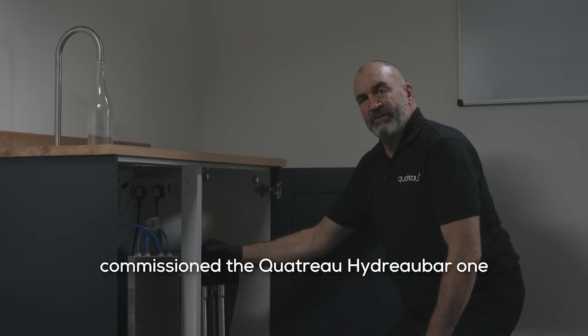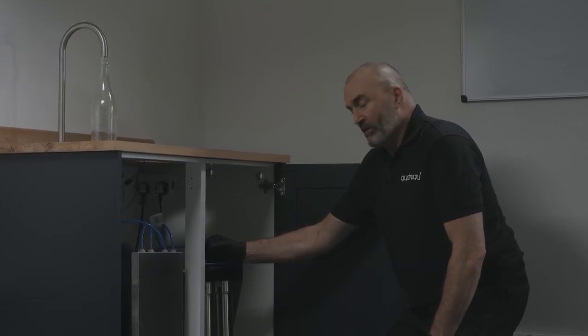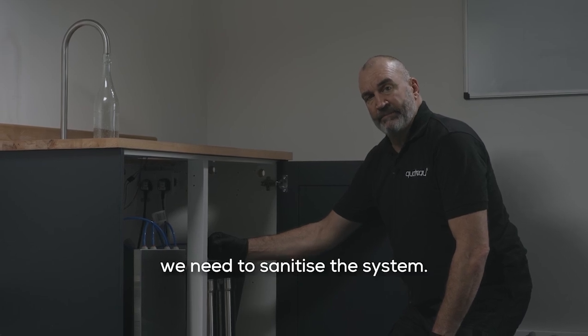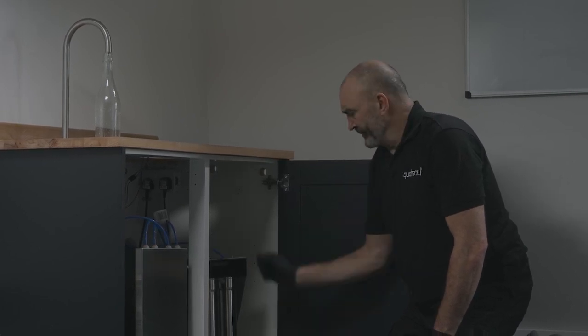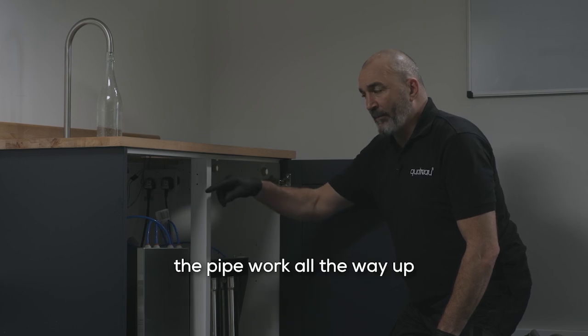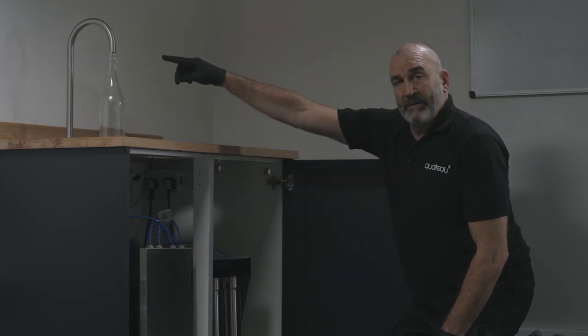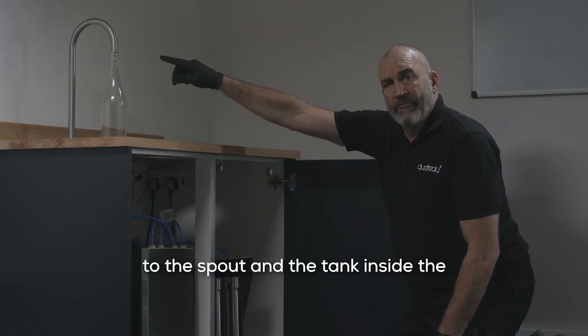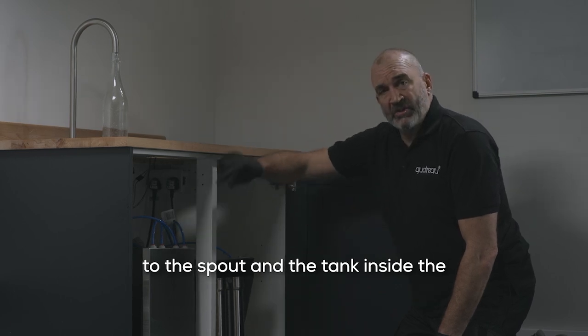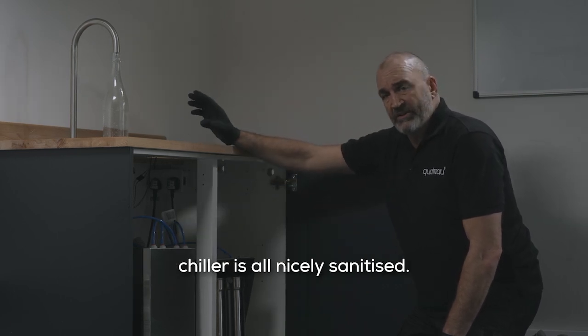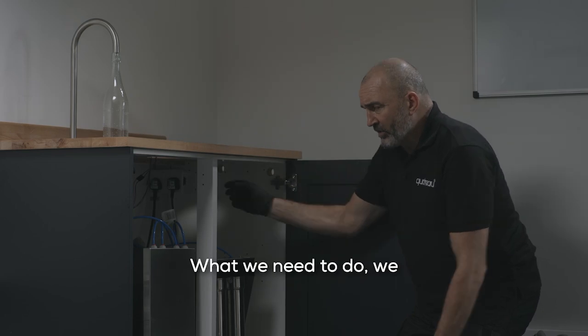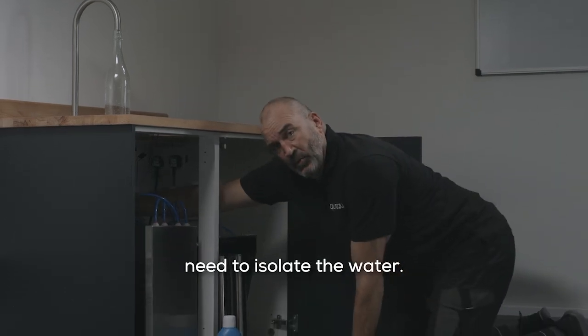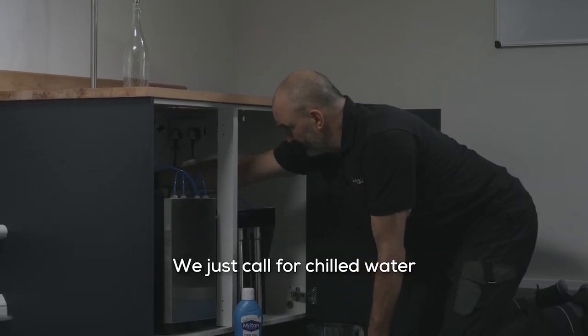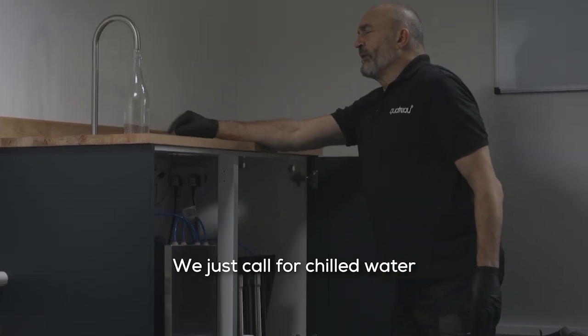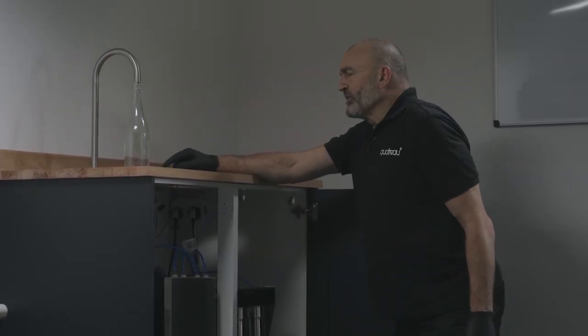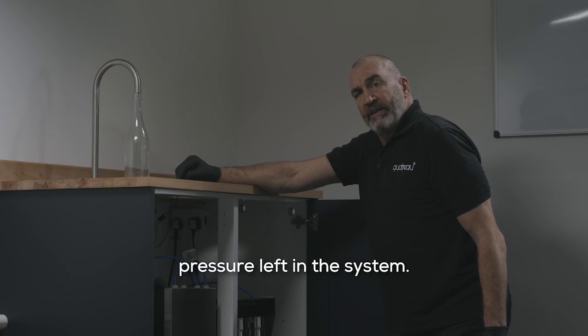Now that we've commissioned the Quatreau HydreauBar 1, we need to sanitize the system. This is to make sure that all the pipe work all the way up to the spout and the tank inside the chiller is all nicely sanitized. What we need to do is isolate the water. We just call for chilled water just to make sure there's no pressure left in the system.